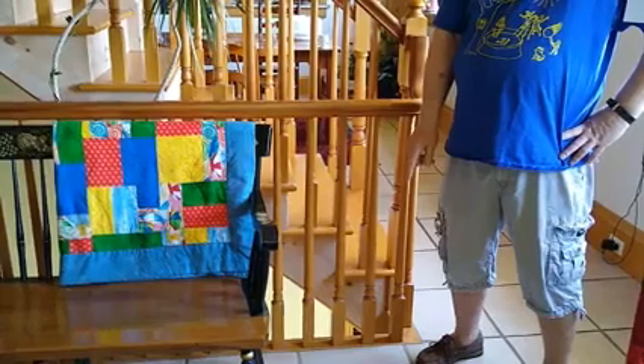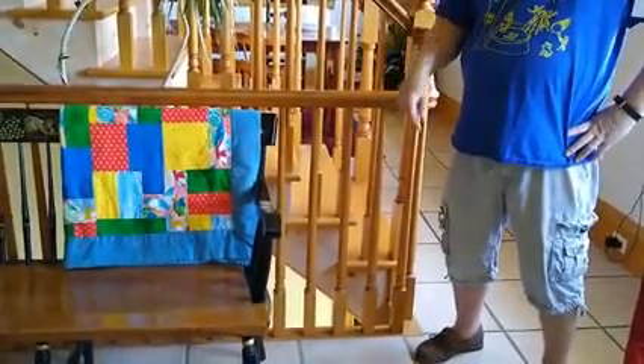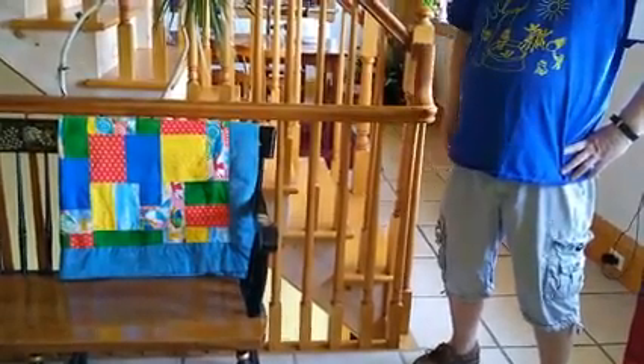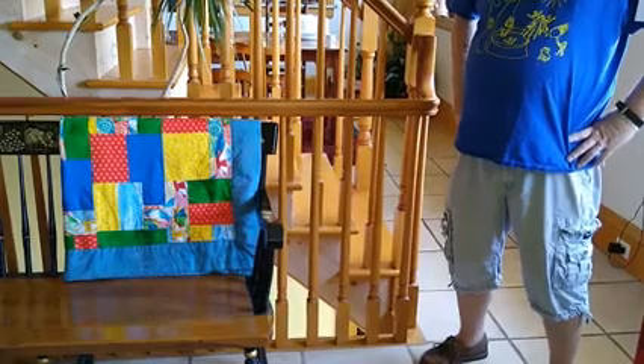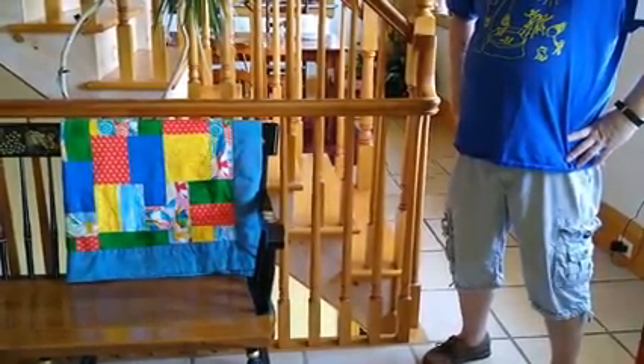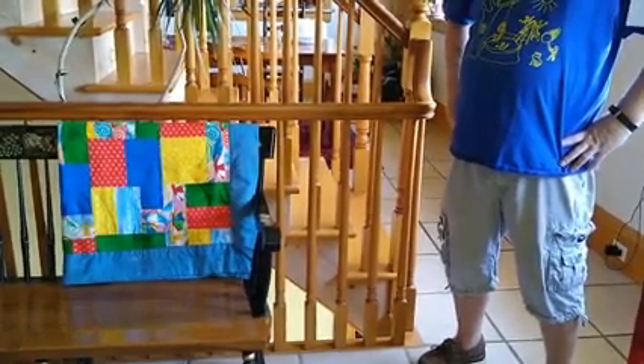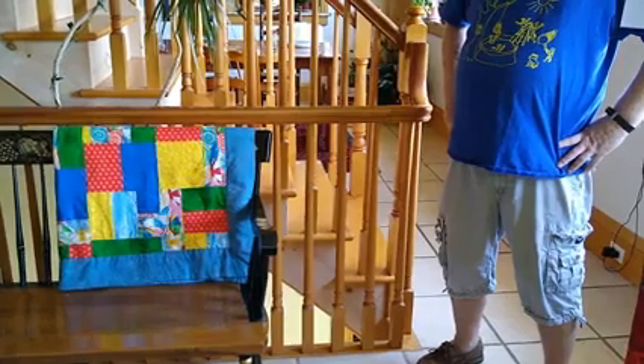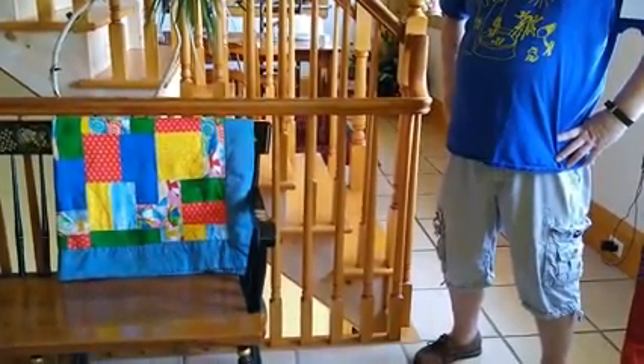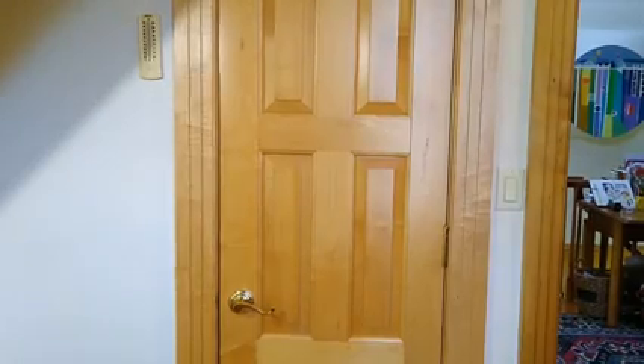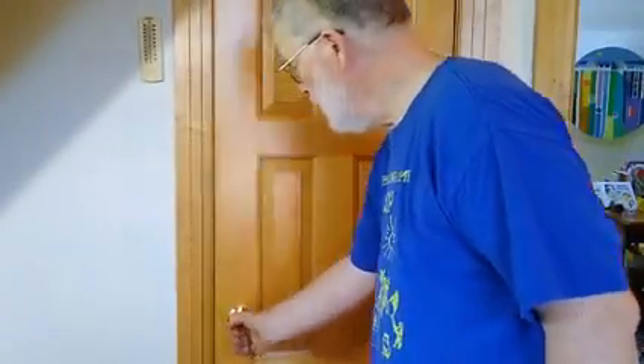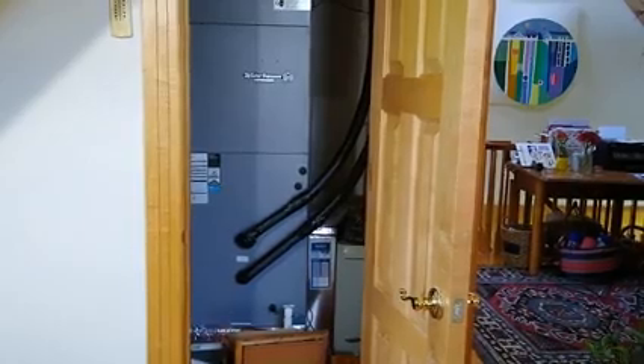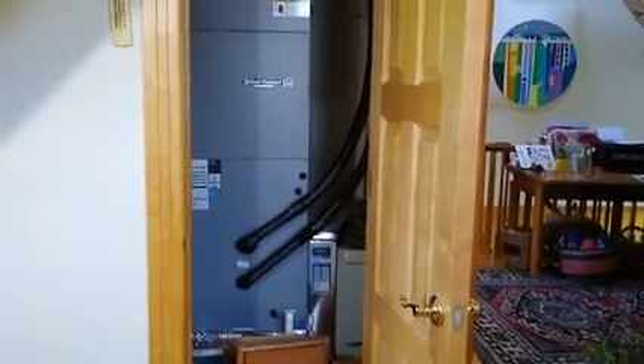Interestingly, the radiant heat of the main floor also radiates upward and downward to heat the downstairs and the upstairs. We call them by those names because the downstairs, while actually being the foundation level, is by design comfortable living space with half of the south-facing windows, making it bright and cheerful living space. As we set it up, the downstairs houses the library with big screen TV as well as the guest suite. A 2-ton chilled water air handler, also by WaterFurnace, hidden in a closet upstairs, provides the air conditioning for the whole house. Calculations suggested a 1-ton unit, but equipment availability led to the installation of a 2-ton unit, which predictably runs only about half of the time.